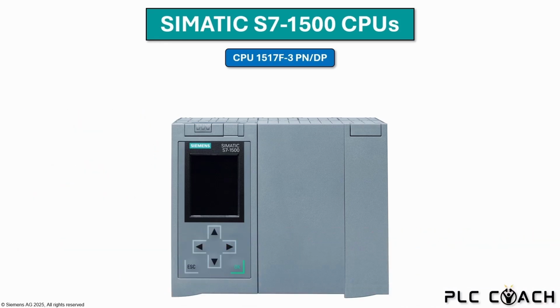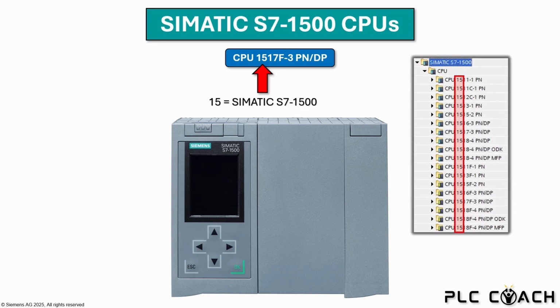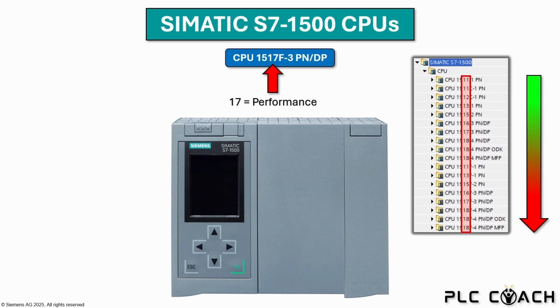Now I want to explain to you what exactly the designation of the CPU stands for. This way, the next time you open a control cabinet, you will immediately have some information about the controller being used. 15 stands for the generation of the controller. It's therefore a Simatic S7 1500. The next two digits provide information about the performance and expandability of the CPU. The higher the number, the more internal memory the CPU has and the more complex a program it can handle. For example, the CPU 1517 has more power than the CPU 1511. Of course, this also has an effect on the price of the device.